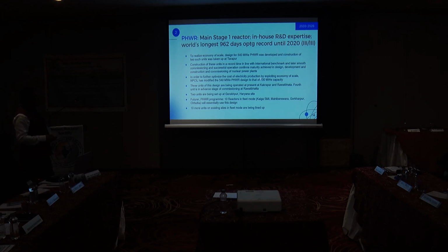Therefore, the next thought was how to optimize the cost of electricity production by exploiting economy of scale, and NPCIL modified the design of this reactor to 700 megawatt capacity. Because it's the same core configuration, only the linear heat rate had to be increased to the level of 220 megawatt, which we already had confidence in. So 700 megawatt was generated. These 3 units are being operated at present at Kakrapar and Rawatbhata, as we have seen in the first slide. The 4th unit is in an advanced stage of commissioning.